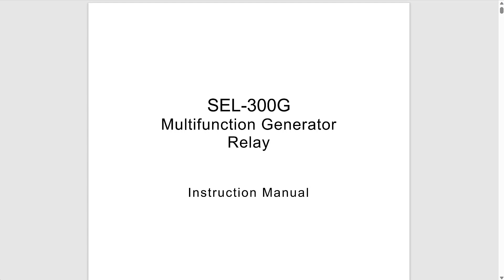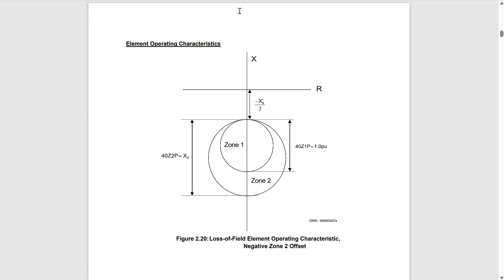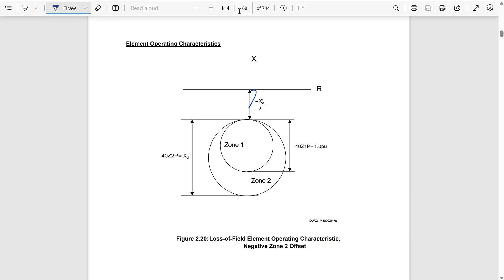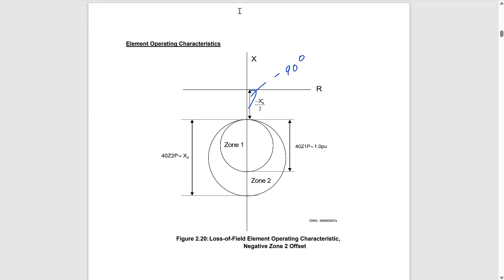In the instruction manual for the SEL 300G relay, on page 68, you can see a scheme that implements two zones — basically two mho elements with a negative offset. Because the impedance will travel from the load impedance to the negative X-axis during a loss of field condition, the mho elements are looking in the reverse direction, that is at minus 90 degrees, so our mho elements are looking in the negative X direction.